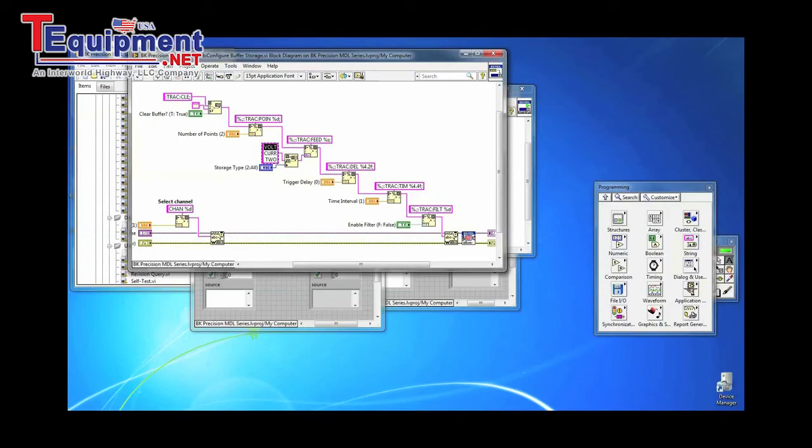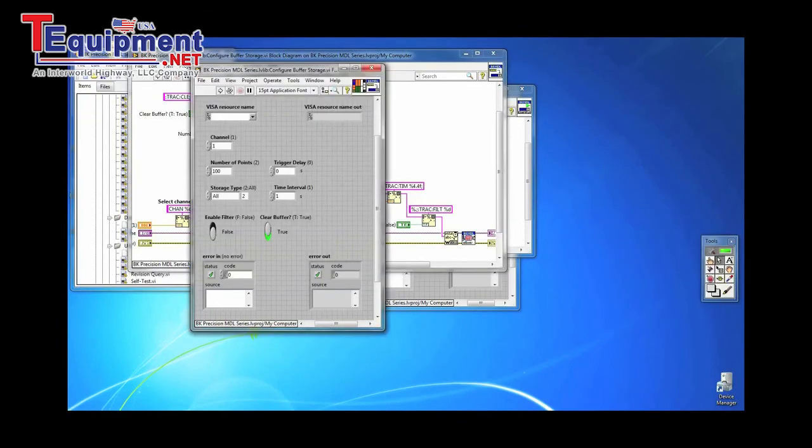VOLT if you want to store only voltages. Change VOLT to CURR if you want only current readings. Or change it to TWO if you want both. However, if you select TWO, the number of points or readings configured earlier will be half. For this example, that would only be 50 readings, half of 100. Now we will just set it to VOLT for voltage readings.